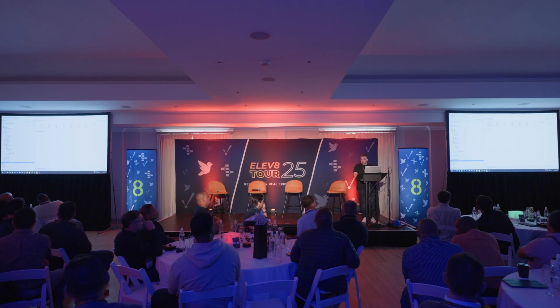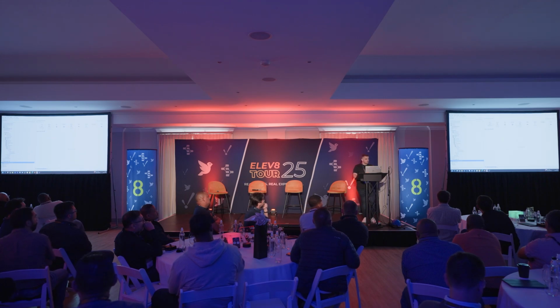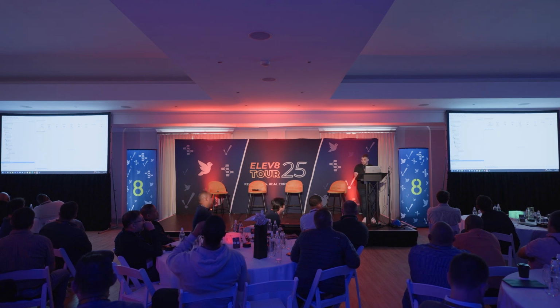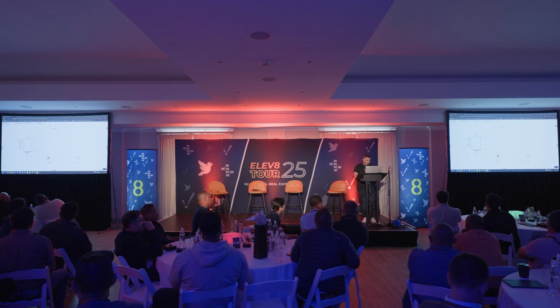When we fail this valve, I'm going to show you our event stream. What we expect to happen is that the valve itself will go into this event stream. The moment the valve has failed more than 3 times, we expect the event stream to log and create the ticket for us. Okay? Telling us, listen, this valve has failed more than 3 times in the past 24 hours, and you should go and investigate. Okay, so let's hope it does that.